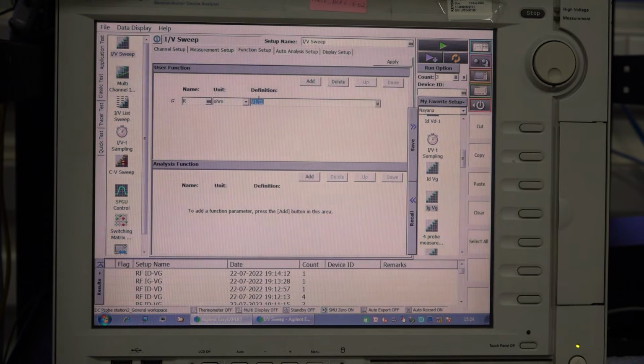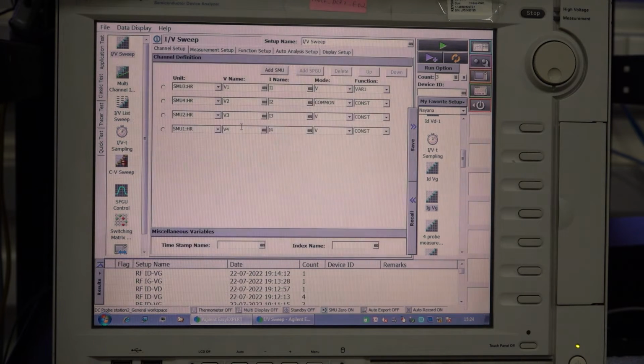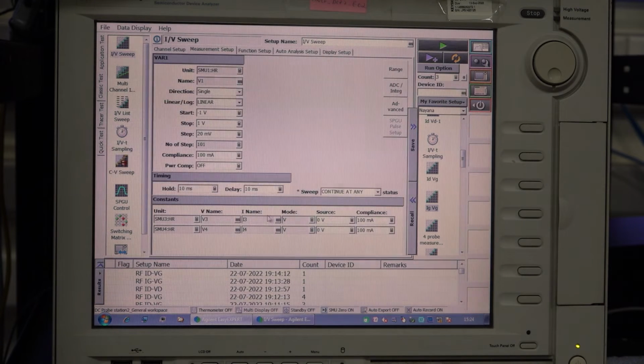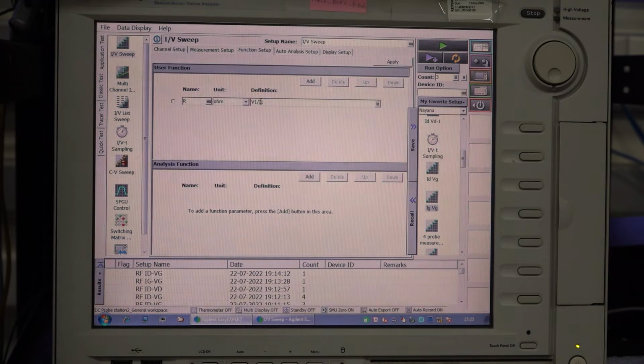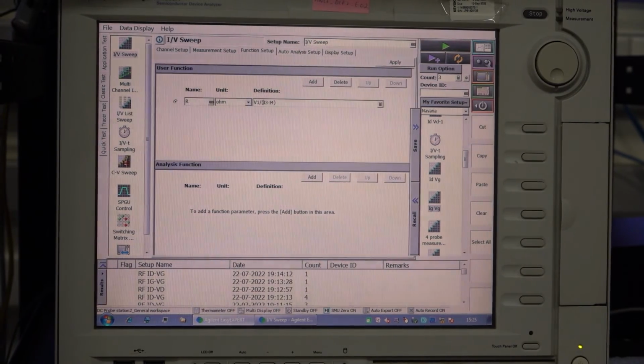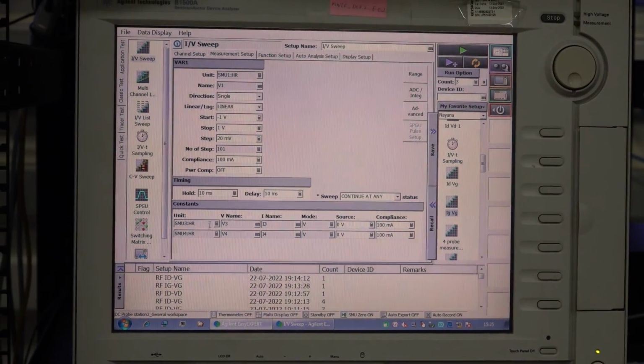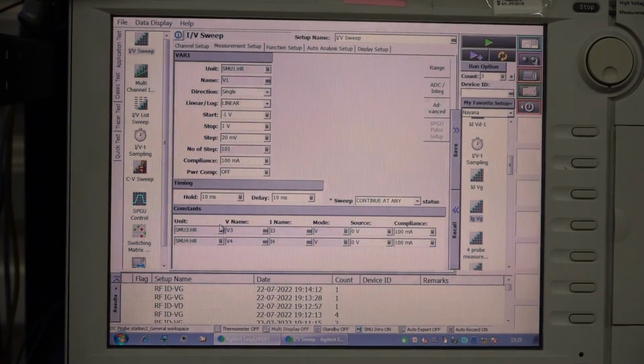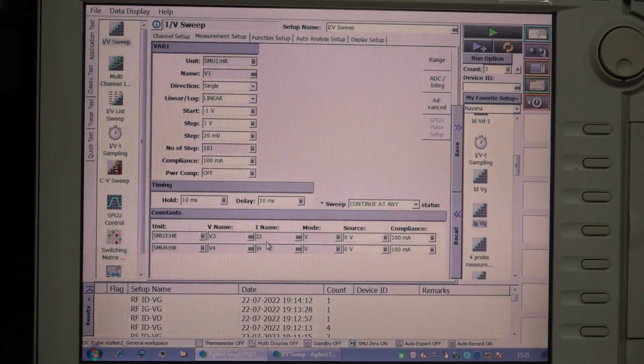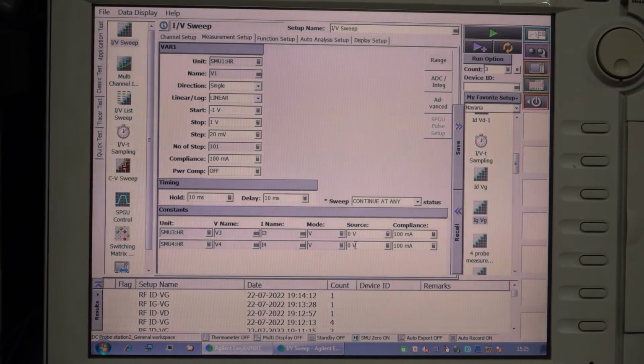So in the function we can write a resistance function which is V1, and for V3 and V4 we have given a... so we have four terminals here. So basically we are giving terminals 1 and 2 for the voltage sweep and 3 and 4 for the current measurement. So if we want to write a formula here, it is V1 by I3 minus I4, okay. So I3 and I4 are here. We are taking the subtraction of these two because we want to measure only one current. We don't know which terminal is high or which terminal is ground or at low potential here. So basically if we give 0, 0 here for both the SMUs, any one terminal will be high and one more terminal will be grounded according to the instrument.